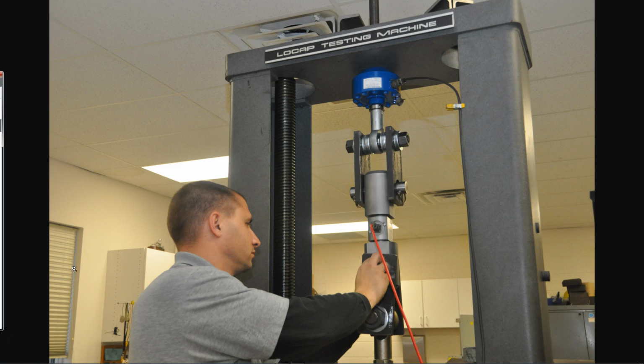Calibration is also highly recommended before or after a critical measurement. So if your piece of equipment just made a critical measurement, then it's highly recommended that you get that piece of equipment recalibrated. Calibration is also highly recommended. In fact, it is absolutely essential after an event. Let me give you an example. After an instrument has been exposed to, let's say, shock, vibration, or physical damage, something which might compromise the integrity of the instrument's readings, then calibration is 100% necessary.